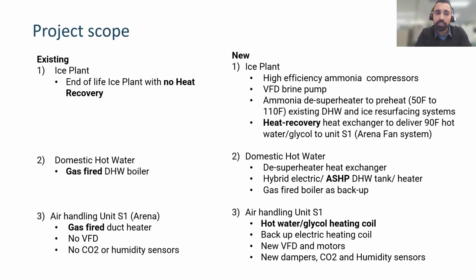So what you're showing here is our existing versus new system. I'm not going to read through all of it, but essentially the ice plant, which was end of life, we are planning to replace with a more energy efficient ice plant. We're adding VFD brine pumps. And we're also adding 2 main heat exchangers. We are adding an ammonia desuperheater, which is utilizing the heat from the ammonia gas, and it is using that to heat up the domestic hot water, which will then be supplemented with a hybrid electric air source heat pump. Also, we have a heat recovery heat exchanger, which will be utilized to preheat the air that will be supplied to the ice rink.